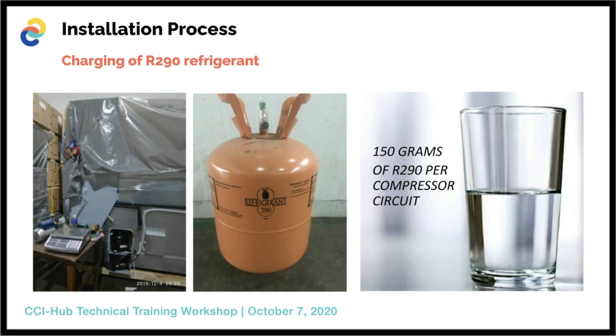The second part is the protocol: the mandatory use of personal protective equipment, or PPEs, is a must. The operating pressure follows a standard, 15 to 25 PSI on the low pressure side, depending on the ambient temperature, especially in the Philippines, as we are in a tropical country. And the high pressure side of the system is 220 to 240 PSI, which is almost the same as refrigerant R22, if you are familiar with that refrigerant. Again, a maximum charge of 150 grams per system is required based on our manufacturer's guidelines.